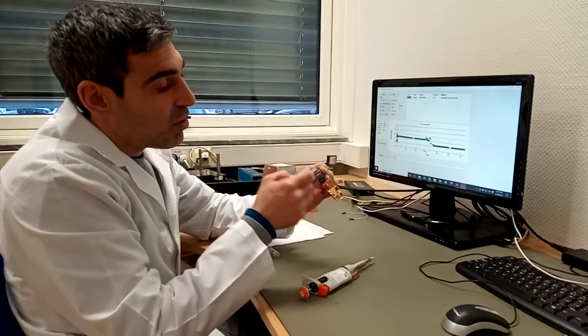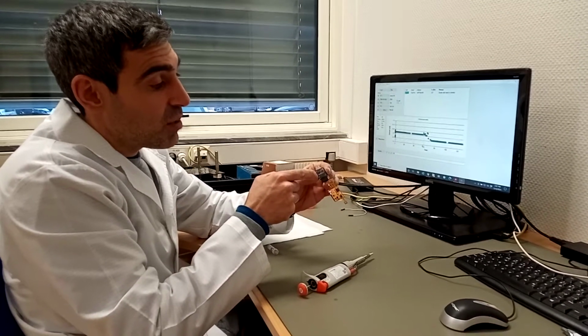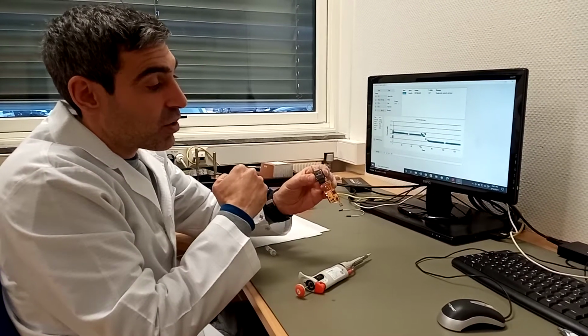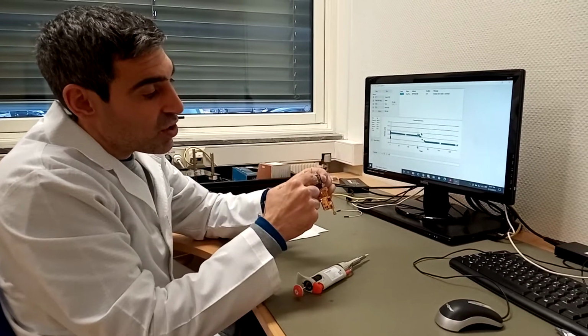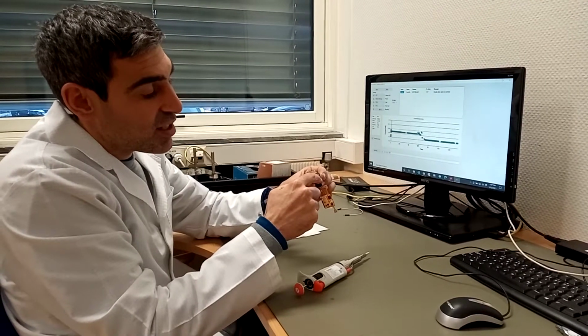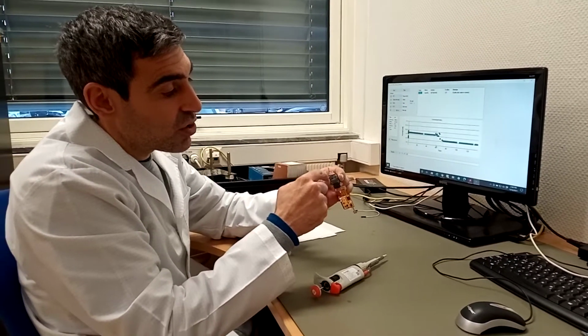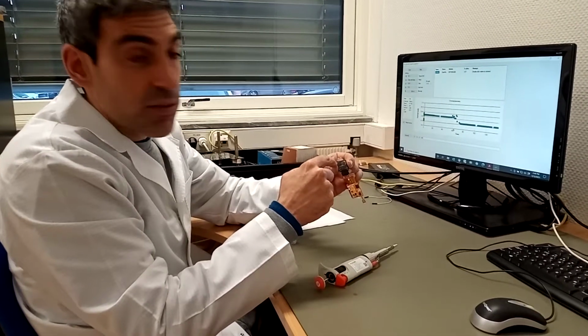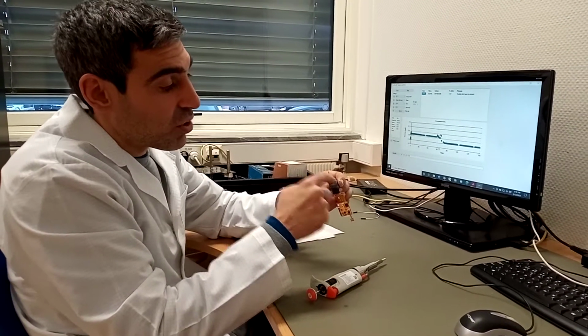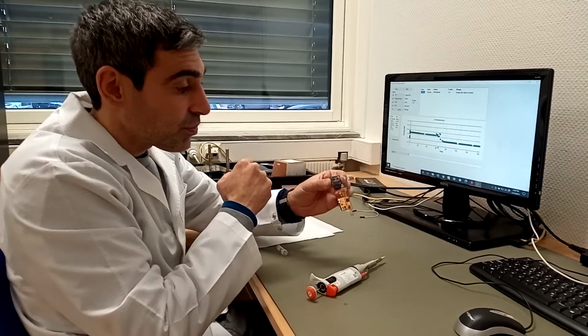And once you have power, you connect our ZP microneedle array sensor. You see you have 2 microneedle arrays on the bottom. They are the working electrodes. On the top left corner, you have a counter electrode. And on the top right corner, you have a reference electrode.